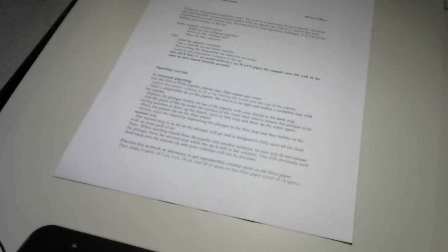What does this mean? This means, are you able to see? This is the minimum volume, and this is the maximum volume you can get when you are using this pipette, okay? So from 0.5 microliter, if we need, say, 4 microliters, we will use this pipette. If we need 10 microliters, we will use this. If we need 20 microliters, we will not use this pipette, right? So now how to set this up?